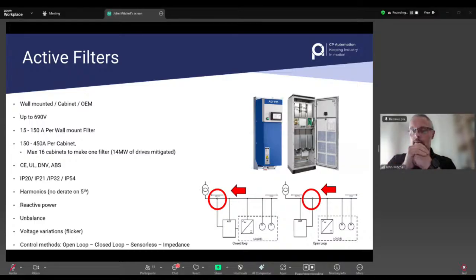This is the Comsys filter, a very comprehensive, robust product with amazing software, and it can also stop issues with resonance and other things because they have impedance control. EV chargers, for example, can be quite problematic to mitigate the harmonics from, and we can do that easily with this product. They go up to 690 volts, so these are LV connection products.